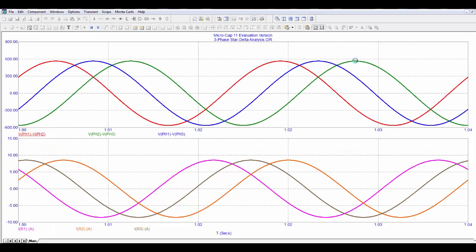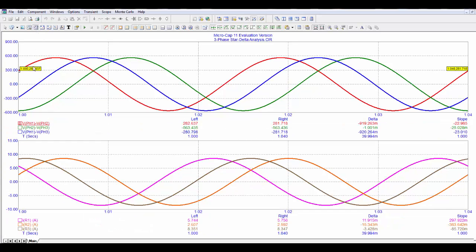Hopefully soon they're going to appear, here they are. And we have up here some line voltages. And if you want to determine what these values are, let me have a look and go for cursor mode. If I click on cursor mode, that enables me to put in some markers up here. So this marker is saying 1.003 seconds, we have 563.418, by the way it's 563.4 volts peak, on the line voltage, which again, is something we're now familiar with.